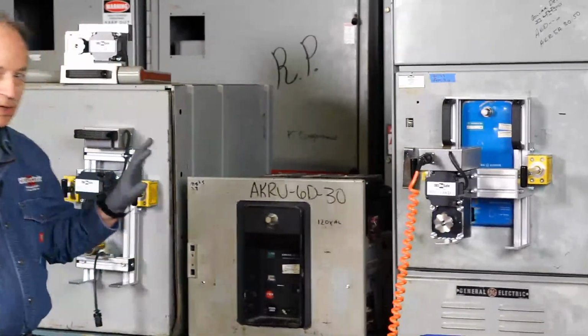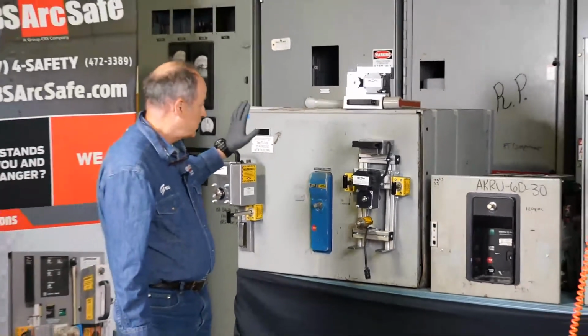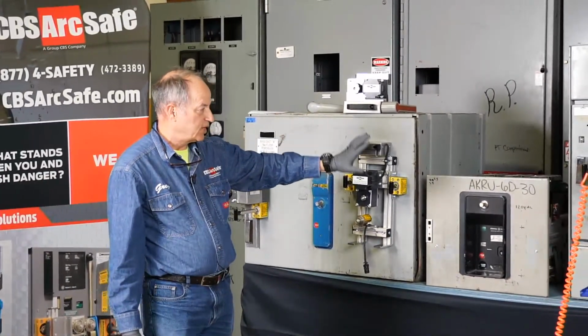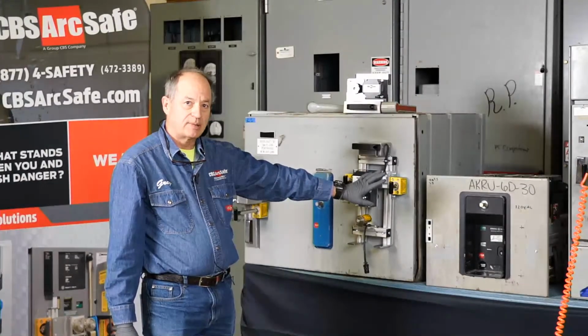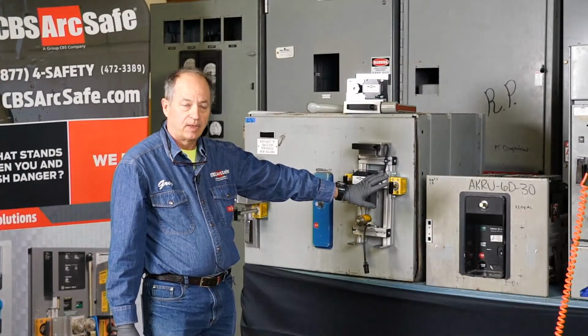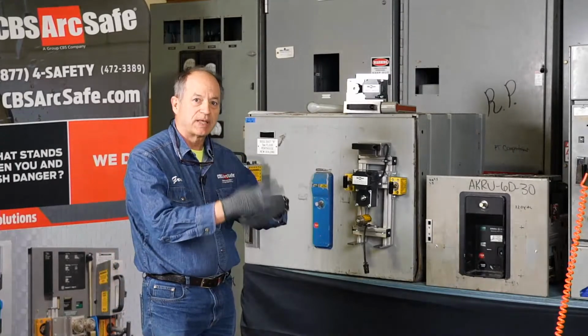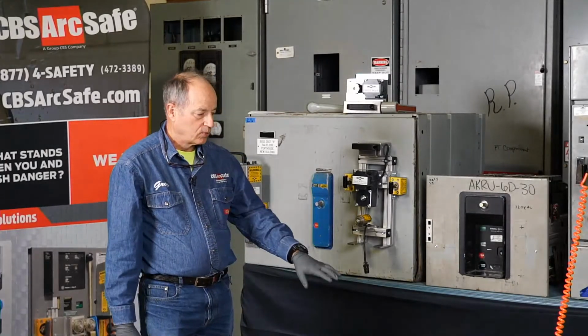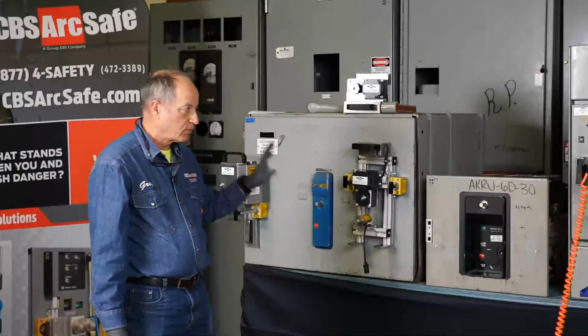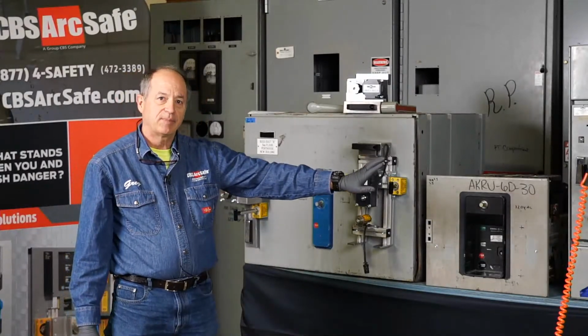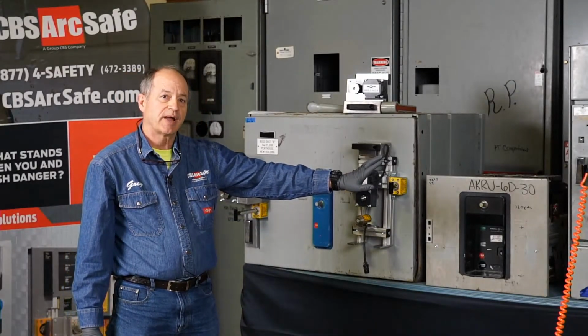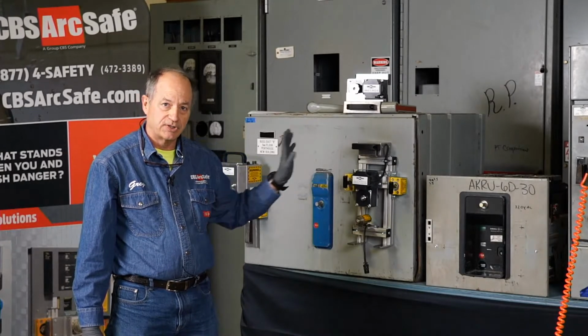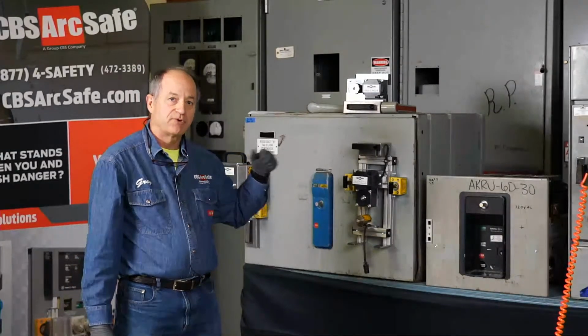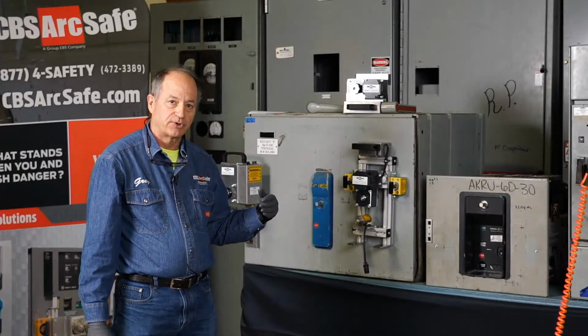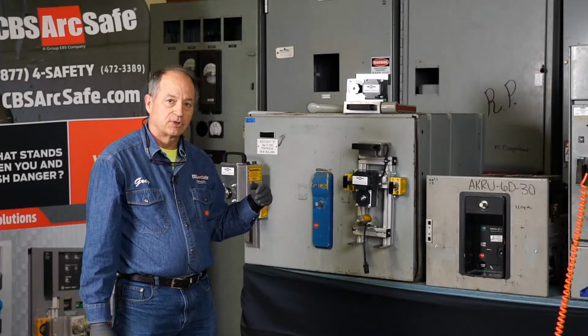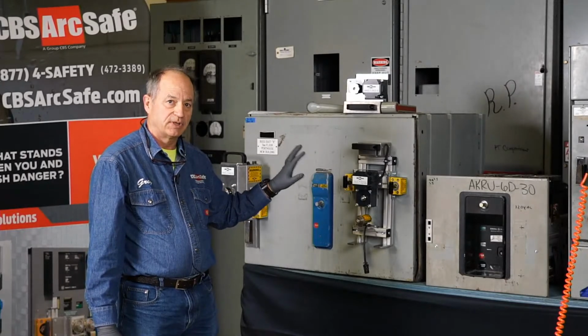Now, just to talk about this: the GE AKD5, AKD6, AKD8 are rotary types of racking mechanisms, and we look at these as mechanical systems. The way the current control module works is we've gone through and found out how much force, in terms of foot-pounds, it takes to rack off and rack on breakers of various amp frame sizes, and then we convert that into amp settings for the current control module to run on, so we don't hurt any of the switchgear.